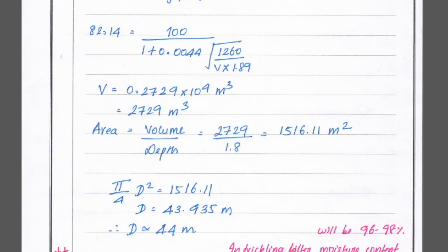Finally, we find the diameter: (π/4) × d² = 1516.11. Solving for d gives d = 44 meters. So the diameter of the trickling filter is 44 meters. This is the method to solve a trickling filter design problem. We will see more problems in the next video. Thank you.